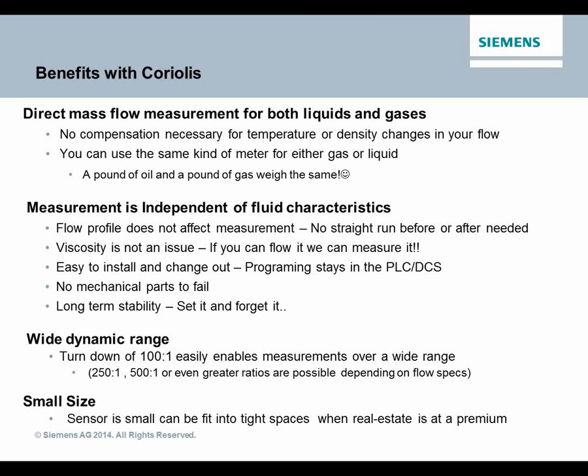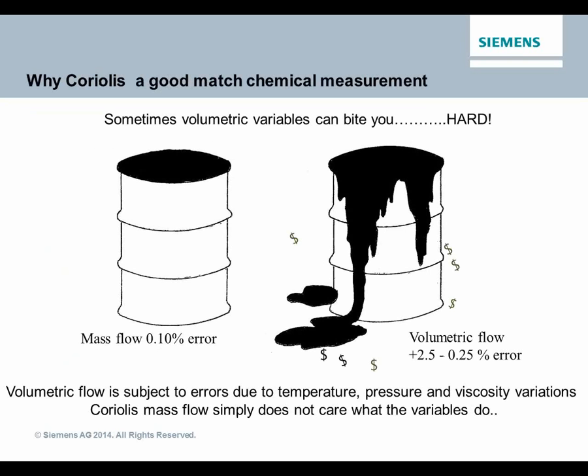Another advantage to Coriolis is the turn down. You know, we hear 100 to 1 turn down, not a big problem. If you're measuring 100 pounds an hour, you can easily measure 1 pound an hour. Well, with a Coriolis meter, it's so accurate and so linear, 250, 500, or even higher ratios are not uncommon. So you buy one meter to measure an awful lot of different things in a lot of different applications. Lastly, one of the newest benefits is the small size. Some of the newest meters are incredibly small for the pipe size that they go into.